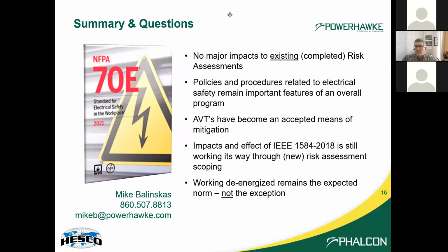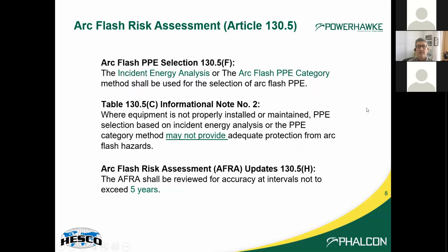If you're talking about an arc flash risk assessment, I think you saw in one of the slides a reference to the PPE method. First of all, you would certainly need to have a copy of NFPA 70E, because if you're going to do it yourself, you really need this sort of cookbook to make the stew. You can't just go winging this stuff. 70E will give you the how-tos on most of that. If you're not going to do the full computer model route, you can use this arc flash PPE category method. Again, as I said, it's like a decision tree on how to select PPE. That's not a bad place to start.